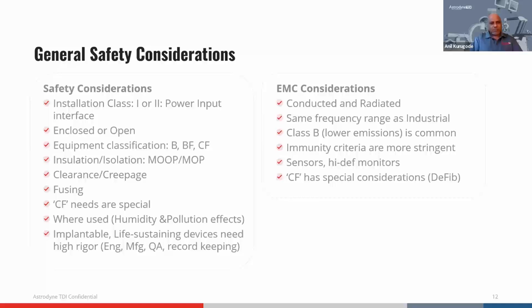For example, in the class 2 world where there is no earth, there's no distinction between line and neutral. So medical systems require that both are fused, because both could be treated as line or live, especially in Europe, since they don't consider neutral as earth, it is considered live. So dual fusing is quite common.